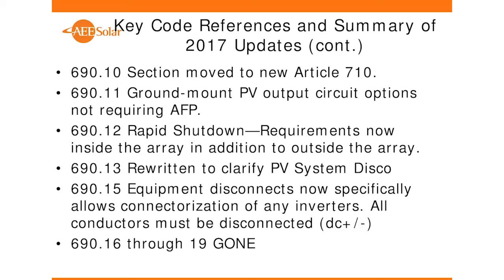But the PV system disconnecting means is rewritten in 690.13. One of the things that, quite honestly, I think we've done a disservice in the code with is that all the requirements related to disconnects are very hard to follow. They're convoluted. They originally started with requirements that were kind of cut and pasted from Article 230 for services, and they've been cut and pasted into PV, which has caused people to generally think of a PV system as a service. And a PV system is not a service. A PV system is a parallel power generator, a parallel power source, which is talked about in Article 230.